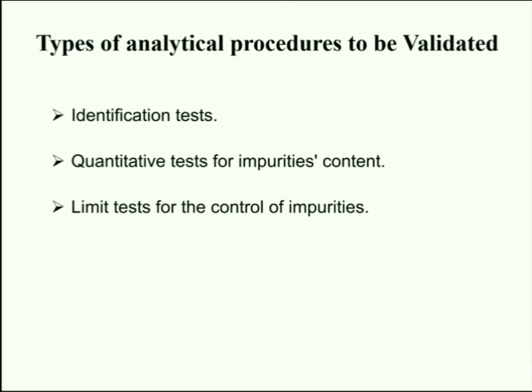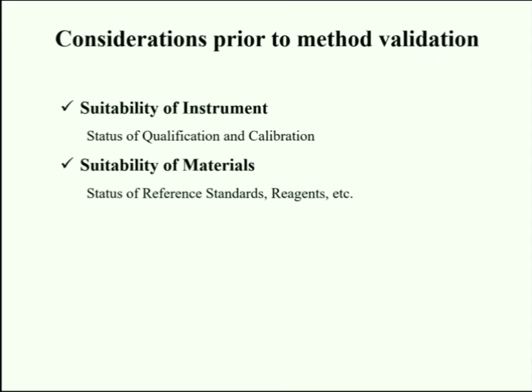Before method validation, there are various considerations which must be followed to define method development goals and acceptance criteria. These include suitability of instrument, which is important for ensuring the status of qualification and calibration of instruments. Next is suitability of materials. This is required for the status of reference standards, reagents, etc. Next, suitability of analyst is for ensuring the status of training and qualification records of the analyst. And the last one, suitability of documentation, is also confirmed for the suitability of the written analytical procedure and proper approved protocol with pre-established acceptance criteria. All of these criteria enable us to determine whether a method has been developed in the way you need it for the control of product quality.